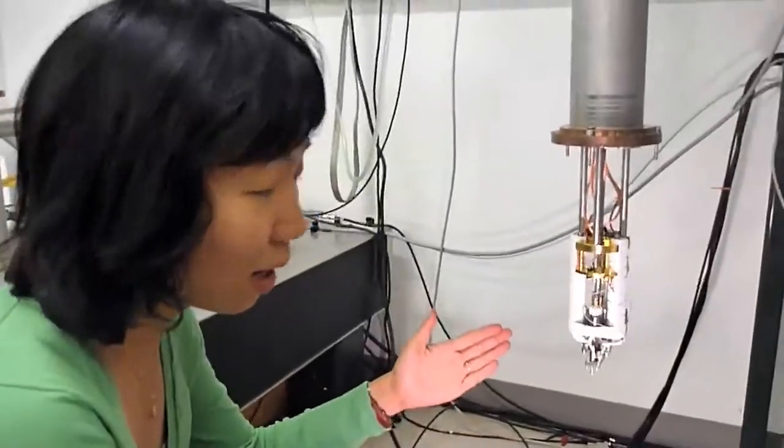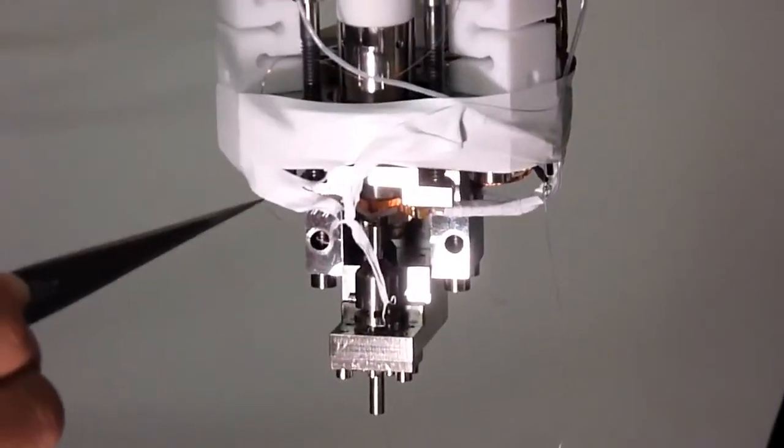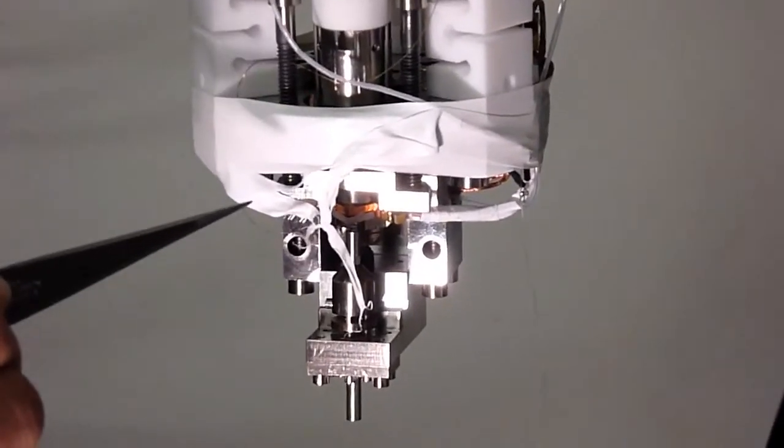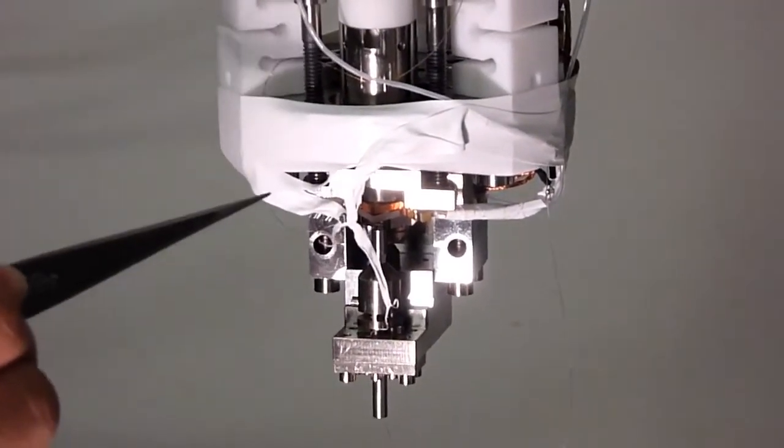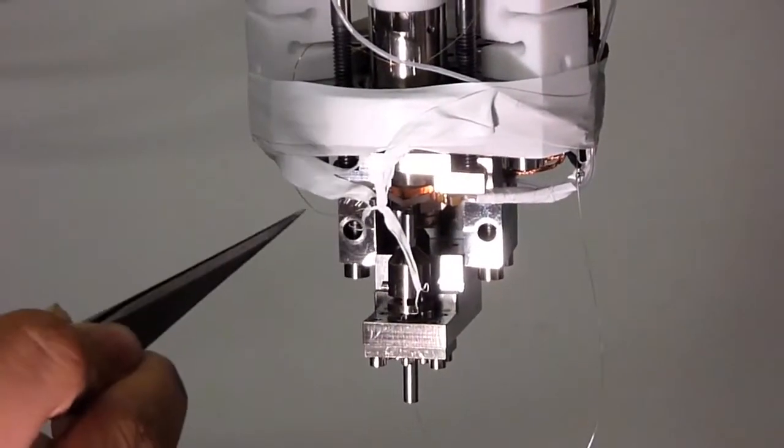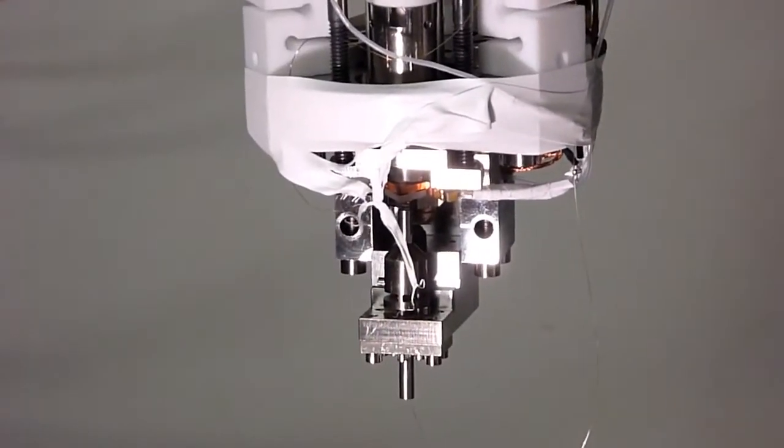Here, as you can see, is the essential part of the MFM. This is a sample holder, and on top of this copper sample holder is a sapphire holder, and on top of the sapphire, it's the sample. And this part pointing up is the fiber and the tip.